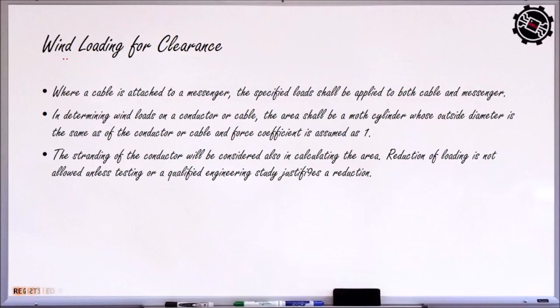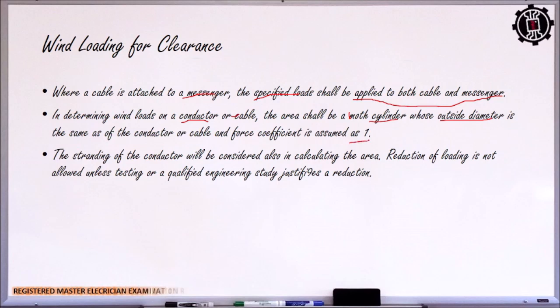Okay. So wind loading for clearances, where a cable is attached to a messenger, a specified load shall be applied to both the cable and the messenger. So in determining the wind loads on a conductor or cable, the area shall be a smooth cylinder whose outside diameter is the same as the conductor or the cable, and the force coefficient is assumed as 1. So the stranding of the conductor shall be considered also in calculating the area. Reduction of loading is not allowed unless testing or a qualified engineering study justifies the reduction. So ano ibig sabihin nito?